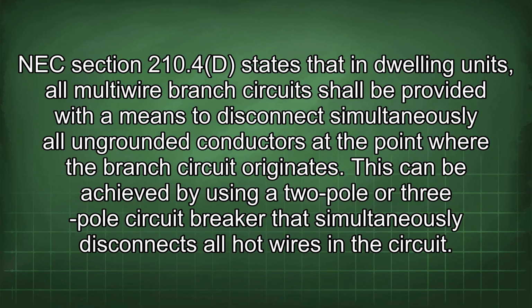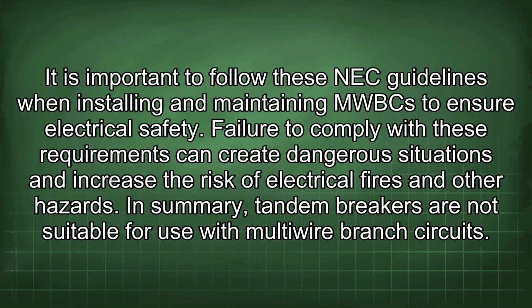NEC Section 210.4d states that in dwelling units, all multi-wire branch circuits shall be provided with a means to disconnect simultaneously all ungrounded conductors at the point where the branch circuit originates. This can be achieved by using a 2-pole or 3-pole circuit breaker that simultaneously disconnects all hot wires in the circuit. It is important to follow these NEC guidelines when installing and maintaining MWBCs to ensure electrical safety. Failure to comply with these requirements can create dangerous situations and increase the risk of electrical fires and other hazards.